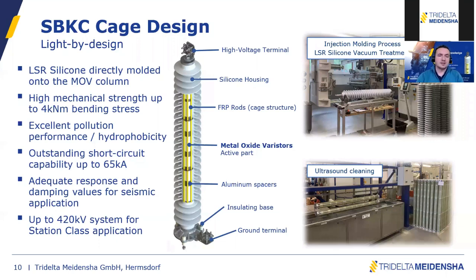And so this is a typical design where, if you are looking for an application up to 420 kV, if cost is an important, driving factor, and you don't have specific mechanical strength requirements, because there is a limitation with mechanical strength. This is a fact. This is the reason why we use it mainly up to 420 kV systems. And this is basically possible if you have a line drop from the conductor. If you want to use it as a bus bar support, this is not really recommended. So there is a limitation in terms of mechanical strength.